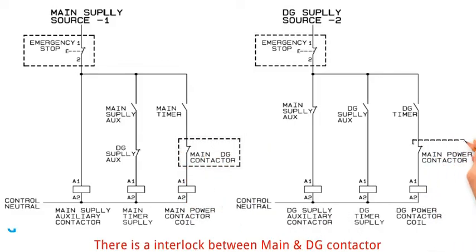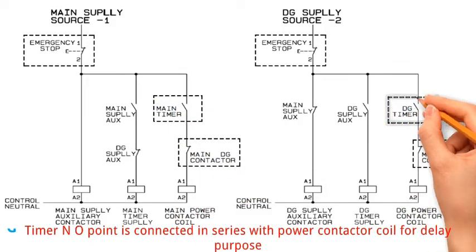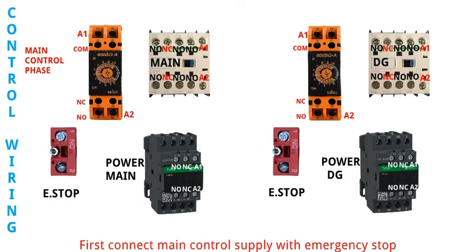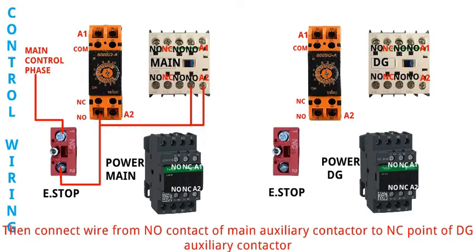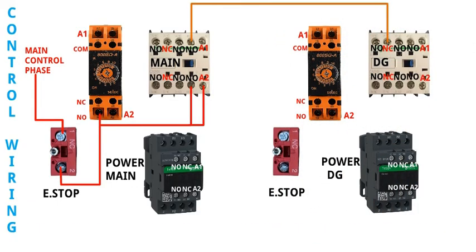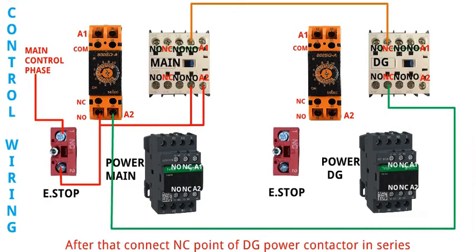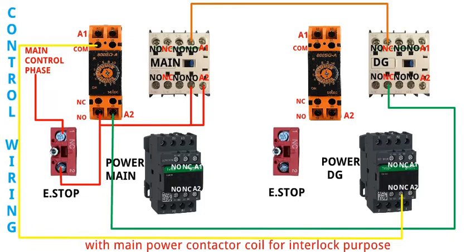There is an interlock between the main and DG contactor. The timer NO point is connected in series with the power contactor coil for delay purpose. Let's start wiring. First connect the main control supply with the emergency stop. After that connect it with the main auxiliary coil, and NO point of timer and contactor. Then connect a wire from the NO contact of main auxiliary contactor to the NC point of DG auxiliary contactor. From the other side of the NC point, connect it with the main timer auxiliary supply. After that connect the NC point of DG power contactor in series with the main power contactor coil for interlock purpose.